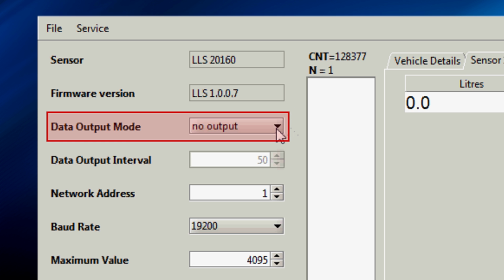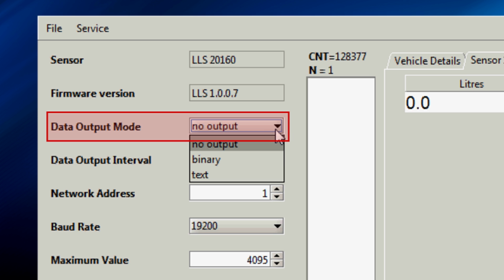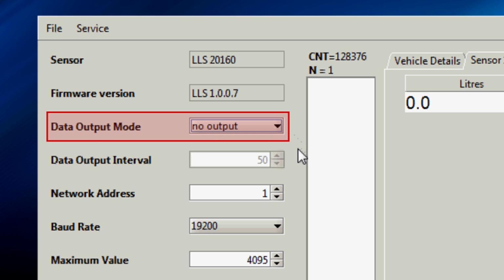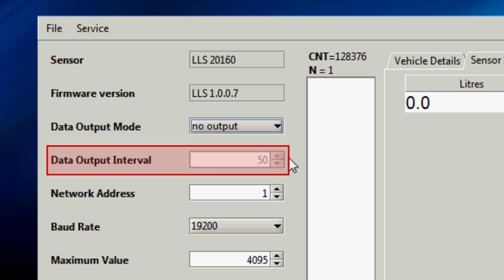The no output mode is used with Omnicomm terminals and the majority of terminals of other vendors. In this mode, data output from the sensor happens only in response to queries from the terminal. In binary and text modes, data output from the sensor happens automatically at the specified interval, which can be configured using the data output interval option.